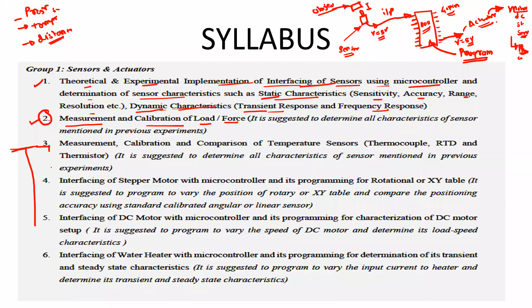Basically, a load cell is nothing but a force sensor. If you apply some weight, suppose it is 1 kg, this load cell will give some signal which is proportional to the 1 kg. Suppose the load cell gives a signal of 1 volt. So the primary signal given by the load cell is nothing but the voltage output of 1 volt. We have to calibrate this 1 volt to the 1 kg. That means we have to assign the value 1 kg to the 1 volt, because software will not identify whether 1 volt means 1 kg. So we have to program the microcontroller to which that load cell is connected, and then we will get the digital output as 1 kg.